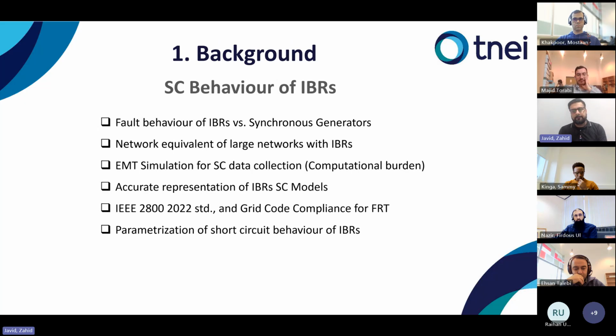And if I talk about just the short circuit behavior of the IBRs, we all know that the synchronous generator's behavior is linear when there's a short circuit. But the fault behavior of the IBRs is characterized by the VSC control employed, especially the FRT strategy, which defines the fault behavior of the IBRs. For conventional generators, we can compute the network equivalent very easily, which is just a voltage source behind impedance. But when we have a network which has IBR units, their behavior is non-linear, so computing a network equivalent for those networks is challenging.